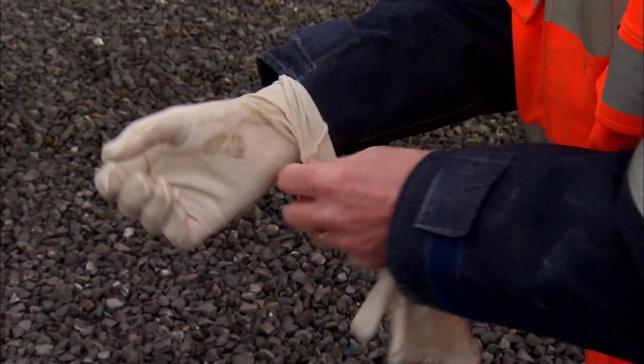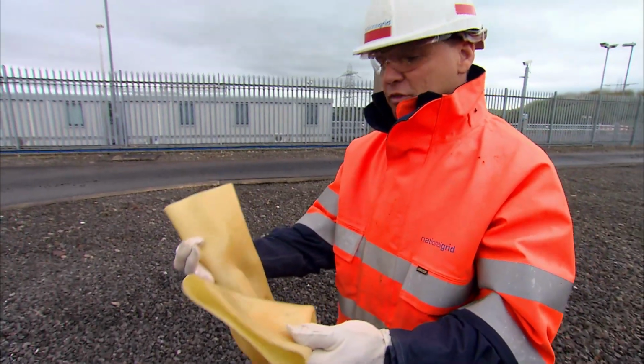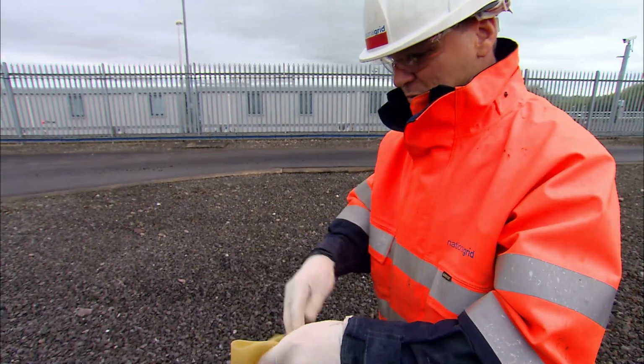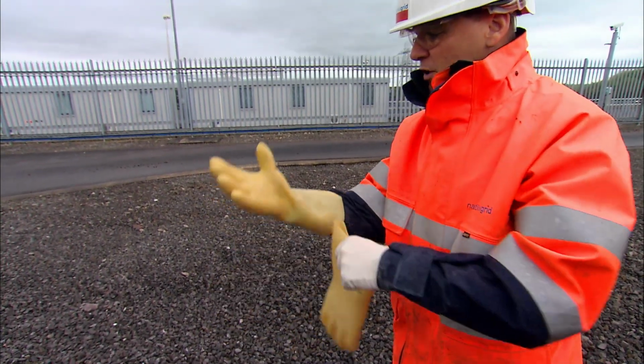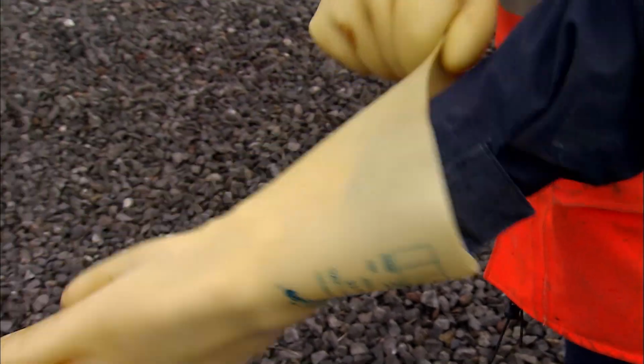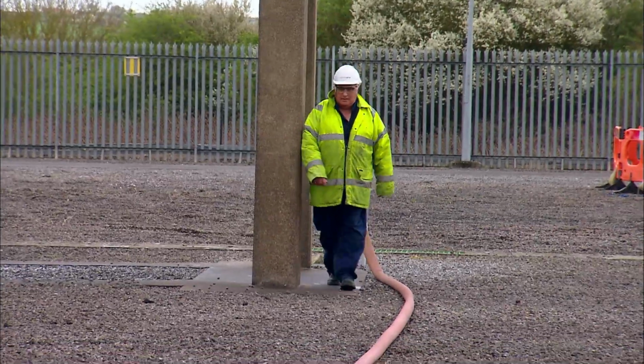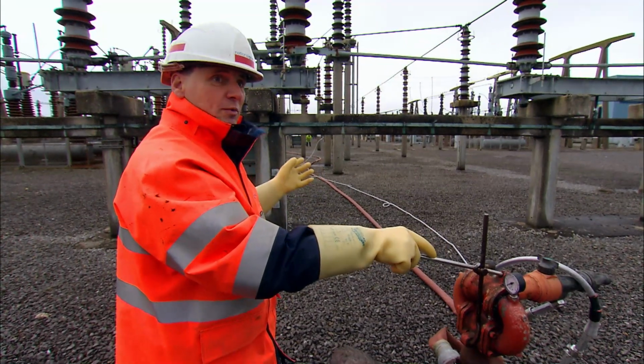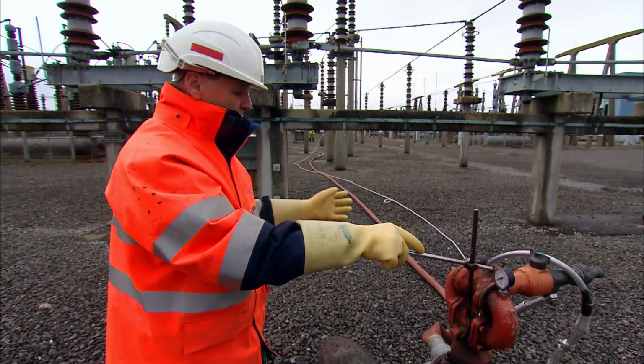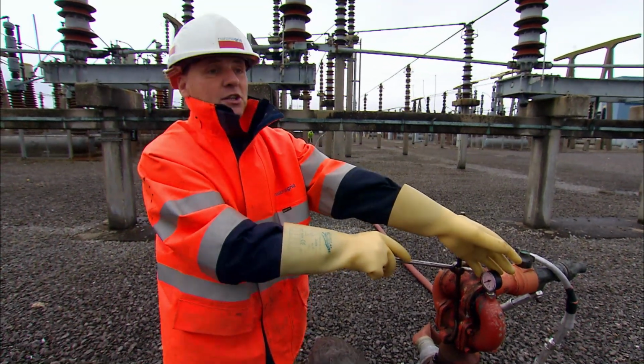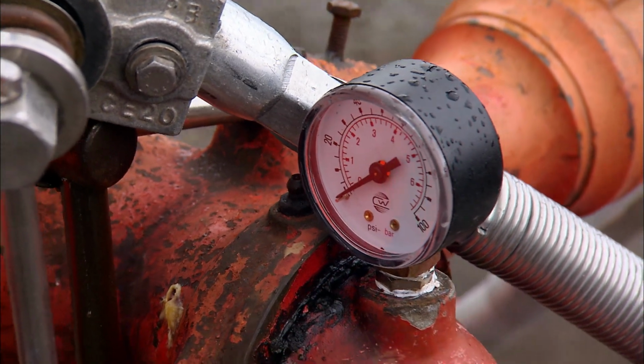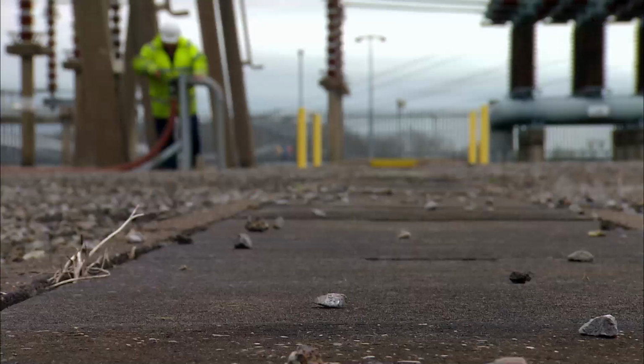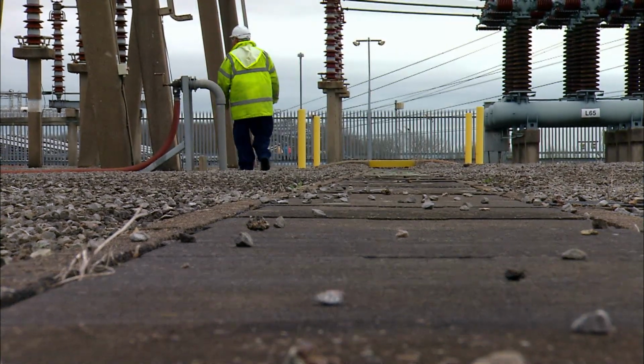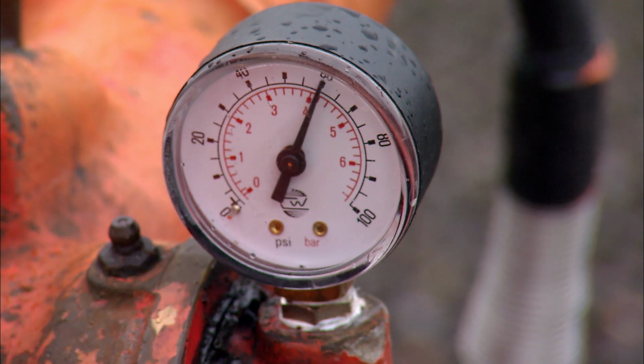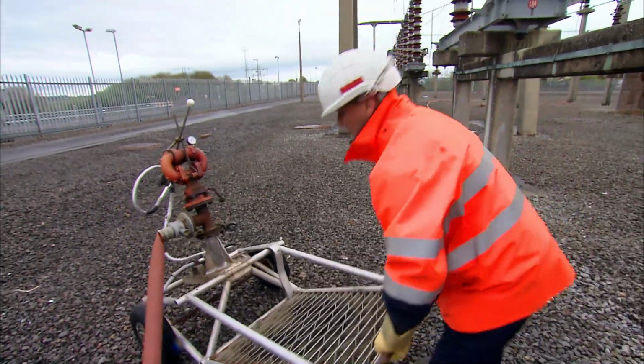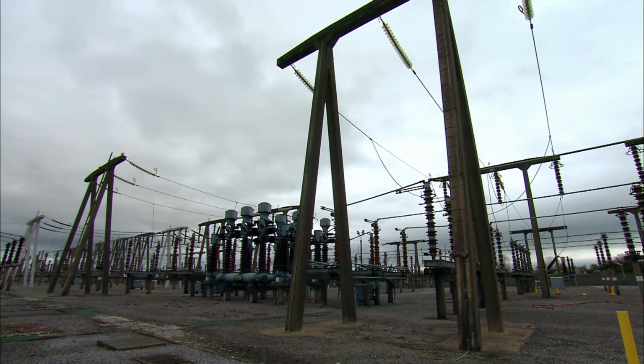One further precaution, the gloves. Well, they're 1,000 volt gloves. So obviously it protects you at 1,000 volts, but apart from that, not a lot more really. With his 1,000 volt gloves on, Pete's ready to wash. I've got to give a signal to Frank. When I give him the signal, he turns the water on, and then we've got to wait for the pipes to charge. I get the indication on the gauge that we're up to the correct pressure, and then I can start washing. When the pressure reaches 80, Pete will send a jet of water onto the live 275,000 volt conductor.